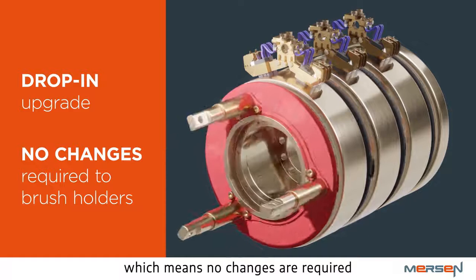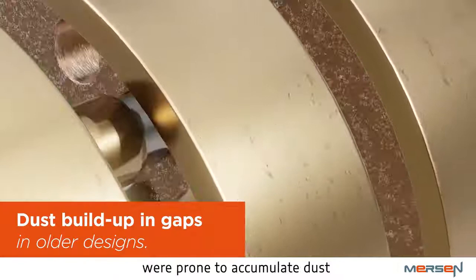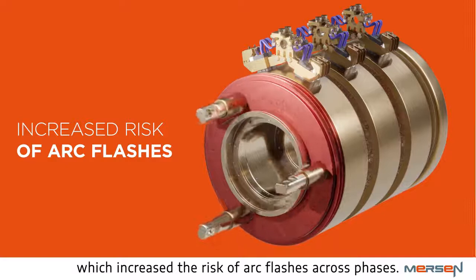The new brush design is also OEM-approved, making it an easy swap at any wind farm. Some of the older slip ring designs were prone to accumulate dust in the hard-to-reach gaps, which increased the risk of arc flashes across phases, and Mersen engineering teams have developed a solution to address this concern.